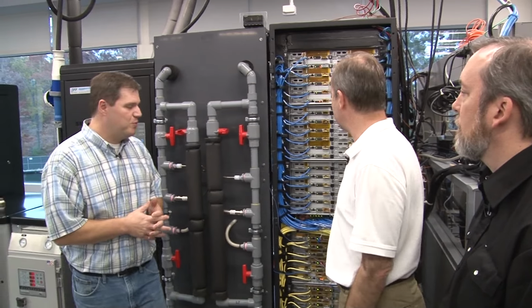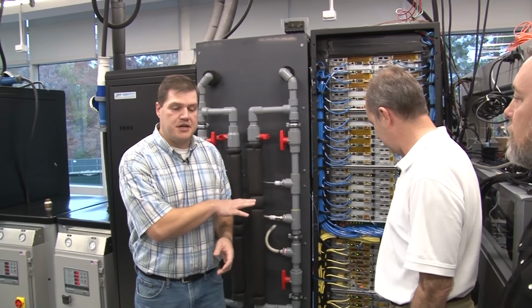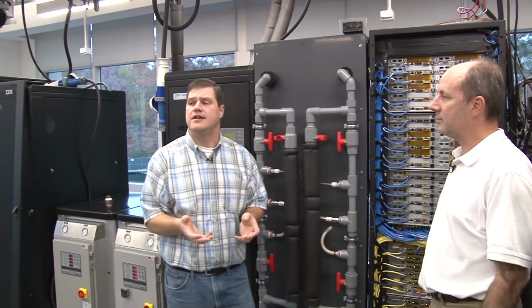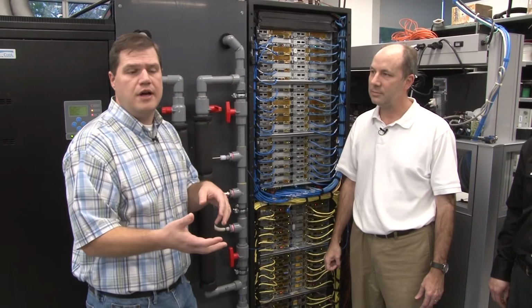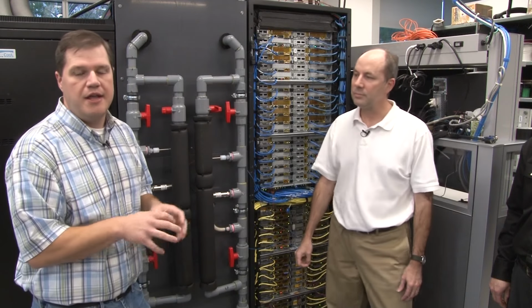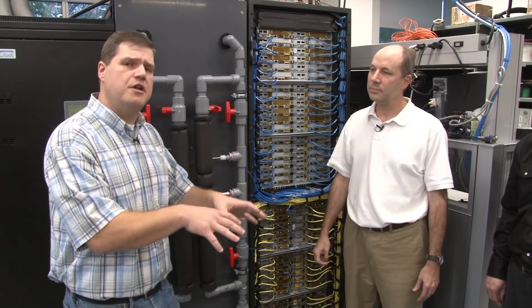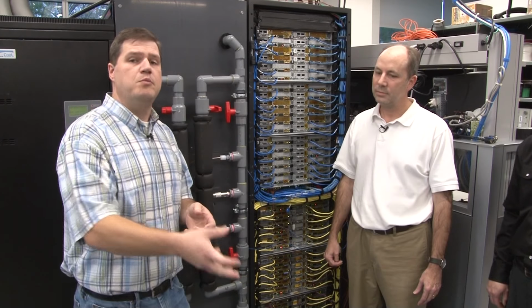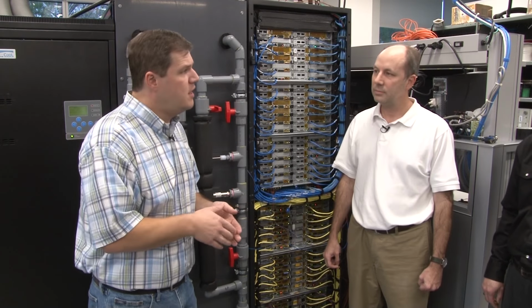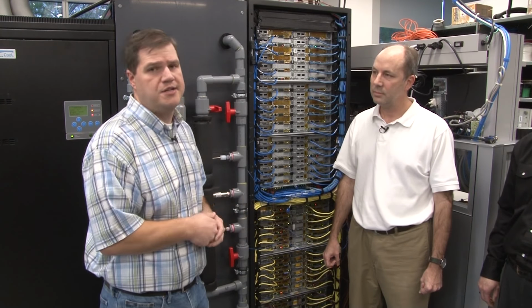Sure, that's a good point. With the water cooling technology, we are removing system fans. So we don't have the need to have any kind of system fans to move large volumes of airflow. We're utilizing the water cooling components and that technology to cool the processors and other subsystem components. So we can remove those systems, which saves power and reduces airflow demands upon the data center.